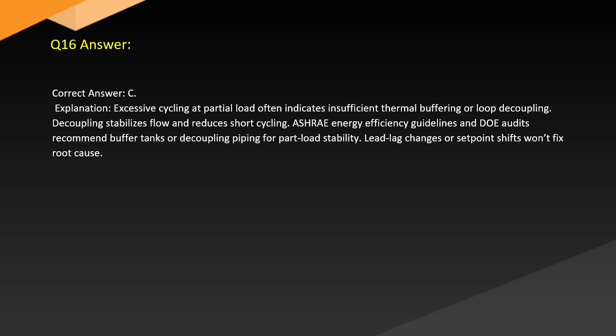Answer. Correct answer: C. Explanation. Excessive cycling at partial load often indicates insufficient thermal buffering or loop decoupling. Decoupling stabilizes flow and reduces short cycling. ASHRAE energy efficiency guidelines and DOE audits recommend buffer tanks or decoupling piping for part load stability. Lead-lag changes or set point shifts won't fix the root cause.